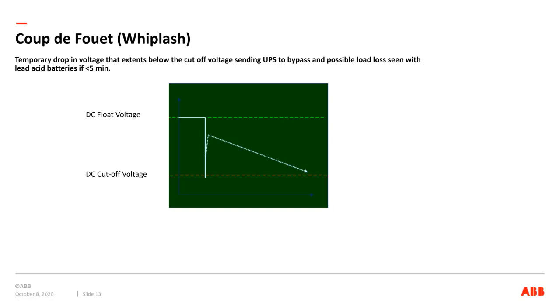I guess that's better English. We actually see that the voltage for the battery string drops and then recoups. And then you have the discharge where it goes down towards the cutoff voltage, and the cutoff is as low as the inverter is able to go, the lowest DC voltage or battery voltage it can operate from. So the coup de fouet depends on the size of the battery relative to the load, and because of this, lead acid batteries historically have not been able to be sized for less than 5 minutes of runtime, and that's 5 minutes end of life.